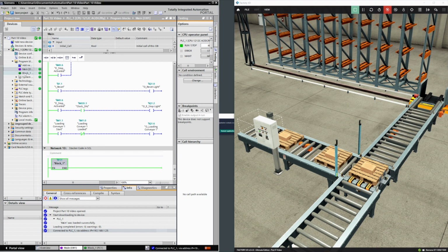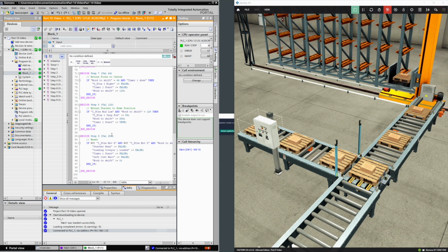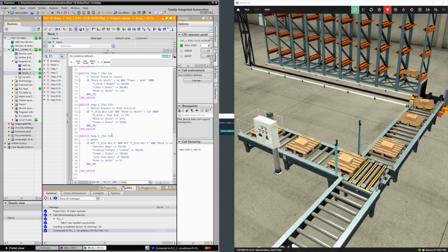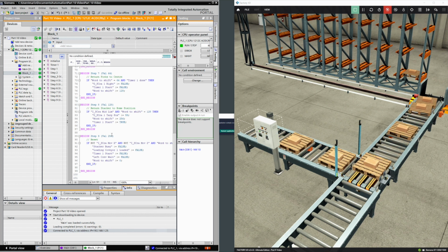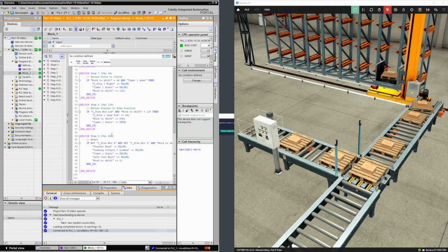Okay, this is where we left off in the last video, video 10, with the pallets making their way to the small loader conveyor to be picked up by the stacker crane forks. The first pallet is picked up and placed in the rack, and then the stacker crane returns home, ready to pick up the next pallet. But as you can see, the small loader conveyor hasn't started, and the next pallet is helped along to reflective sensor 5 by the transfer left conveyor and then goes onto the forks at an angle.